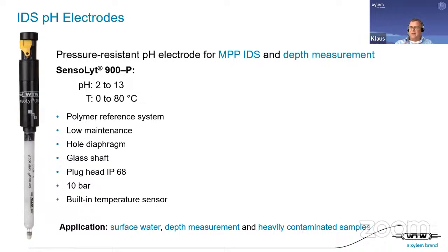This is an electrode with a polymer filling, and it has no diaphragm. It has simply a hole, and that makes it very insensitive against pollution. So it's pressure resistant up to 10 bars, and of course it has a built-in temperature sensor. It can also be used in heavily contaminated samples. From time to time, you even have in a laboratory some very difficult samples, which could also have some electrolyte poison. For this, this electrode is also an option because of this polymer filling and a long way to the reference. It will take a long time before an electrode poison can harm this electrode.